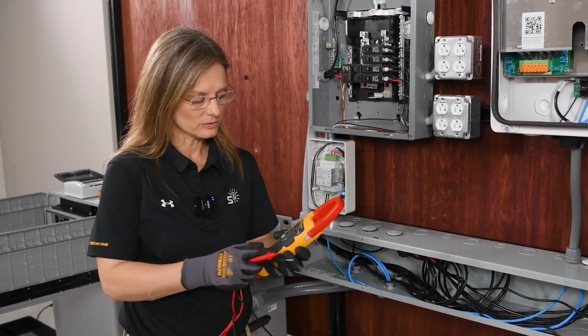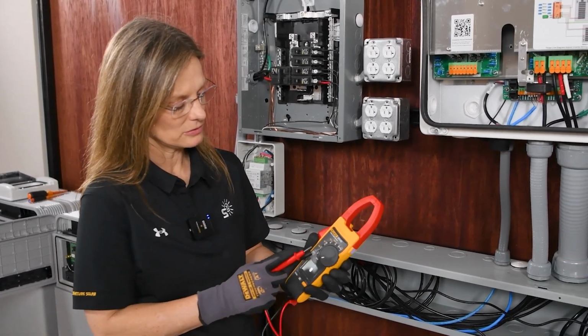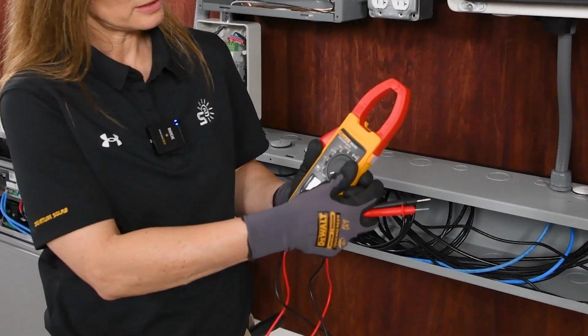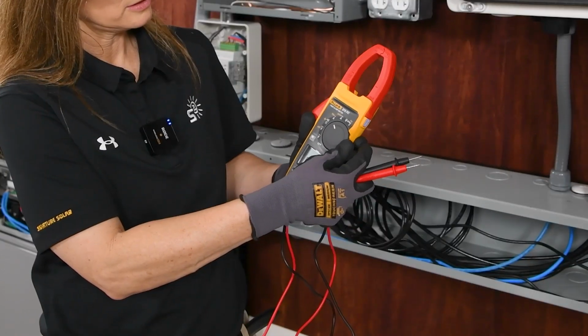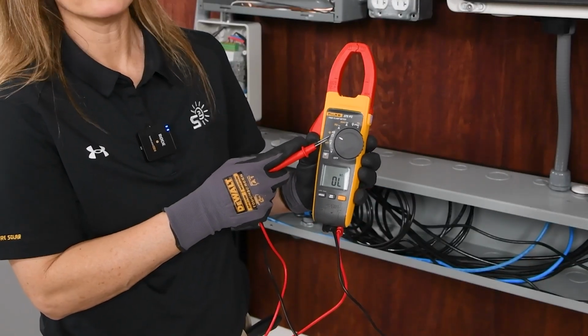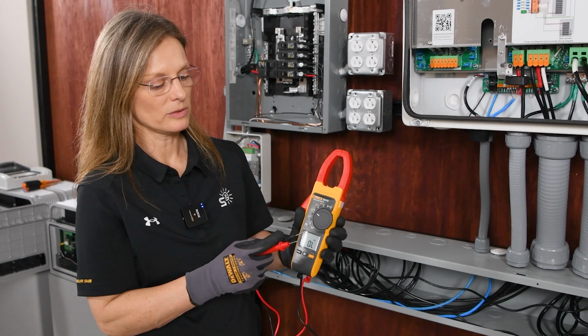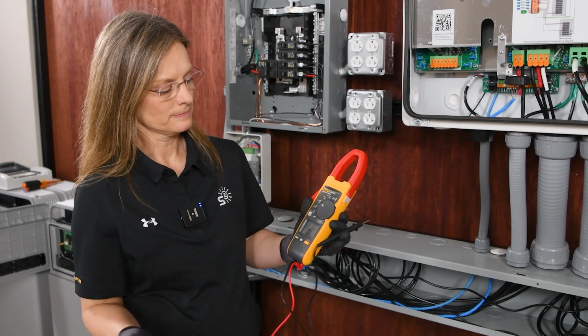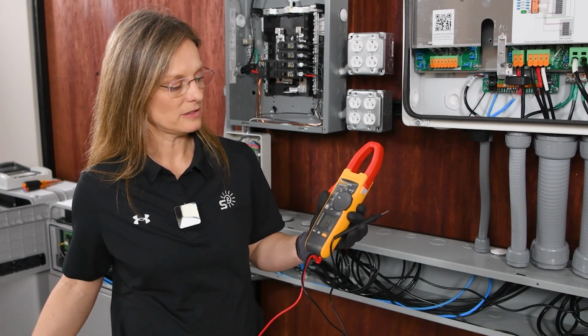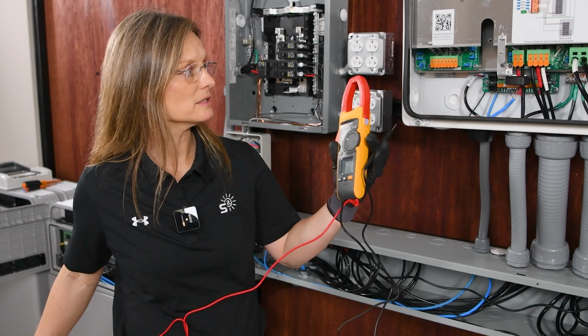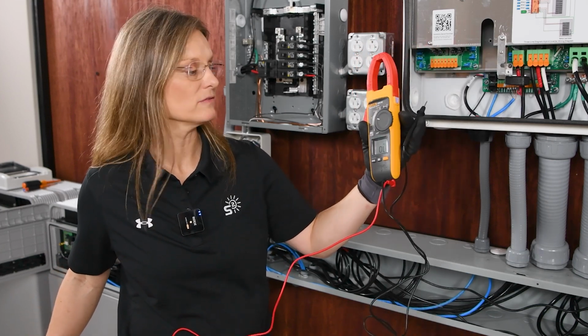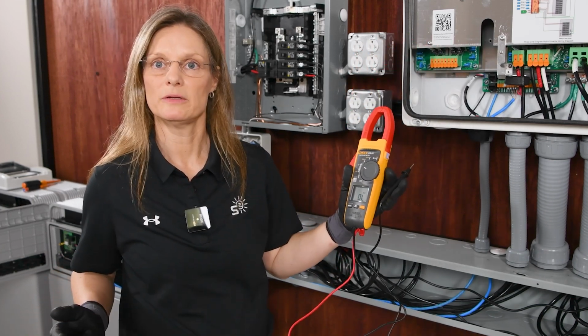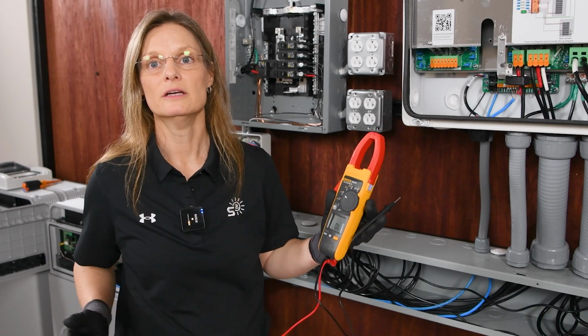To do that, we will turn our multimeter on to the ohms or continuity test, which is the indicator right here. When we check, putting one probe into the positive of our batteries and one into the battery input on the inverter, we'll listen for a beep. That means that we have good continuity across both.